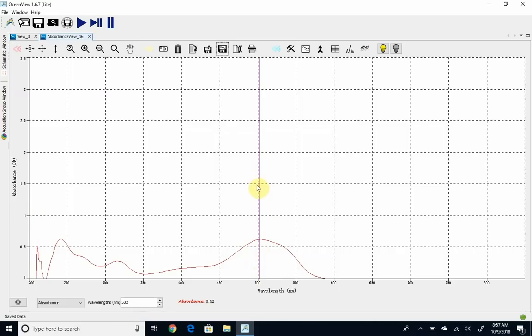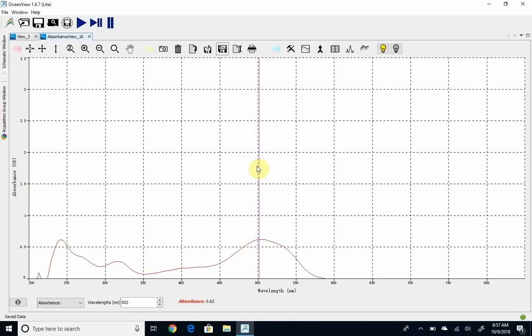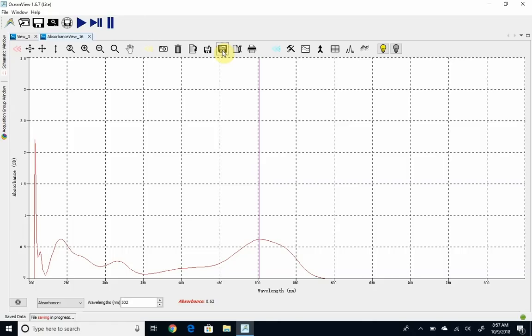You can move around, but I want you to notice my absorbance maximum is about .62. Anywhere between .1 and about 1.5 is good. If you're above 1.5, you're going to get a lot of noise. Your data calculations aren't going to work very well. But this looks good. I don't need to dilute the sample or do anything different with it. So I'm going to go ahead and record the absorption spectrum. And it's pretty much done.